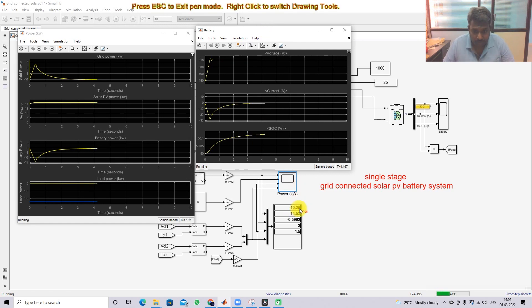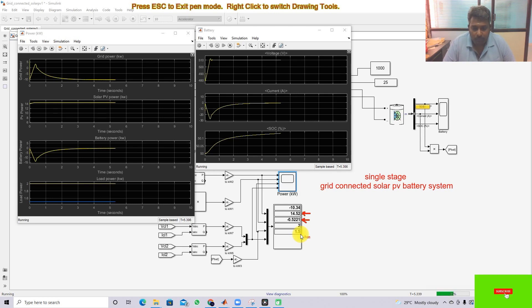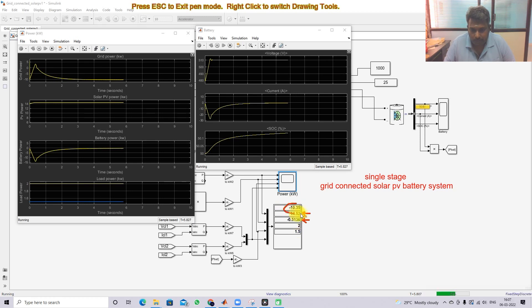The grid power is around −10 kW, solar power is around 14.52 kW, battery power is around −0.5 kW, and load power is 2 + 1.5 = 3.5 kW total. The solar PV charges the battery and supplies the load; the remaining power is fed to the grid. This is the working of the model under 1000 W/m².